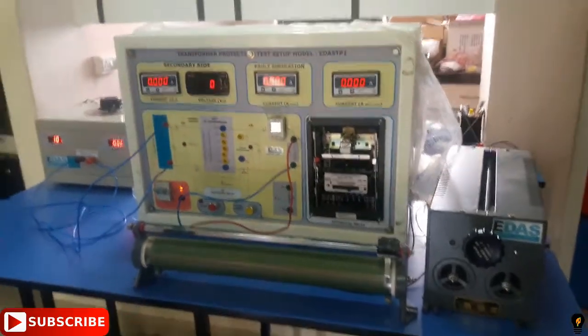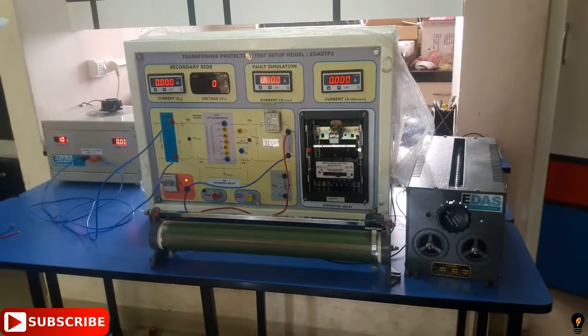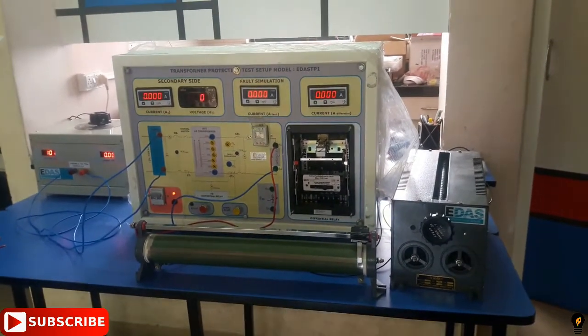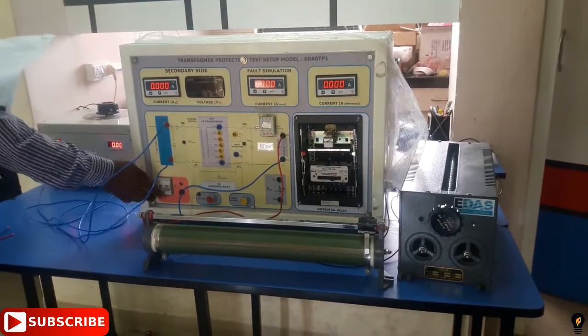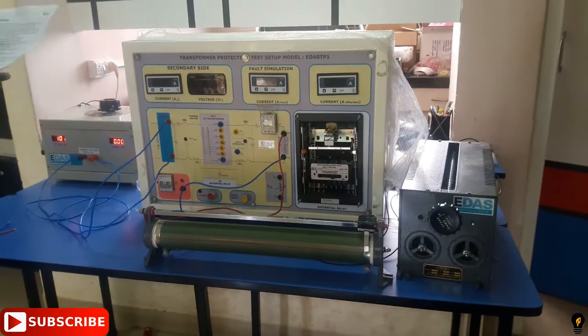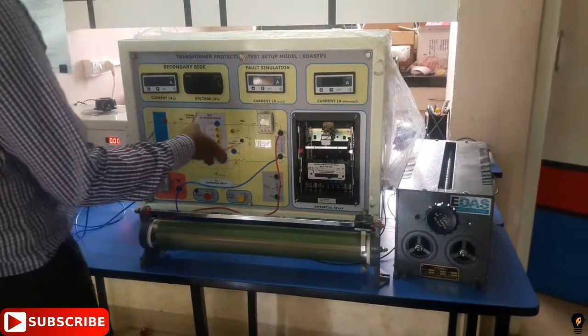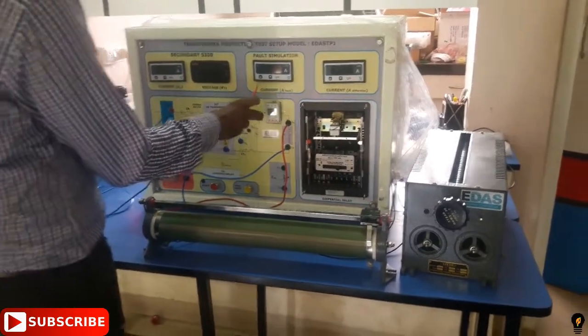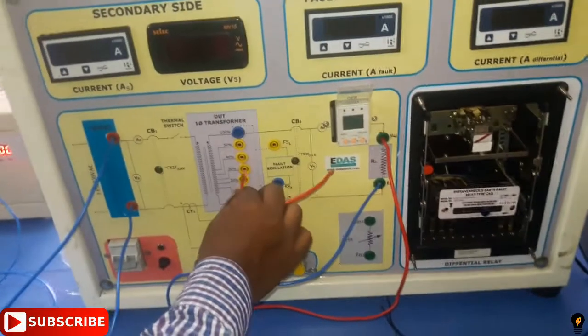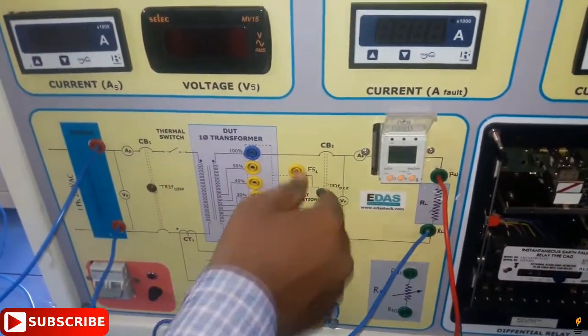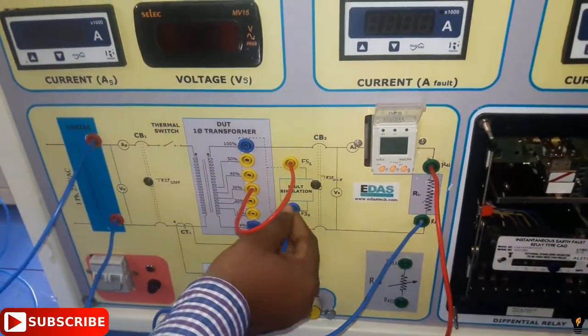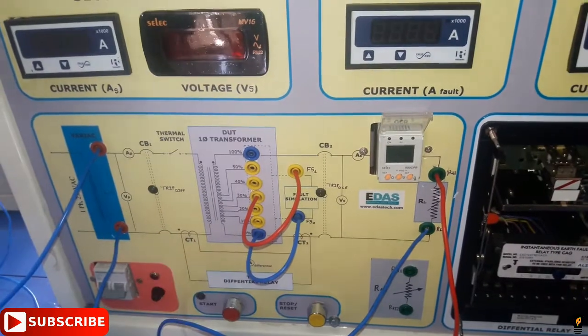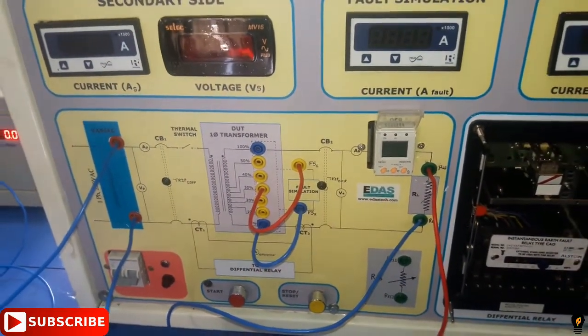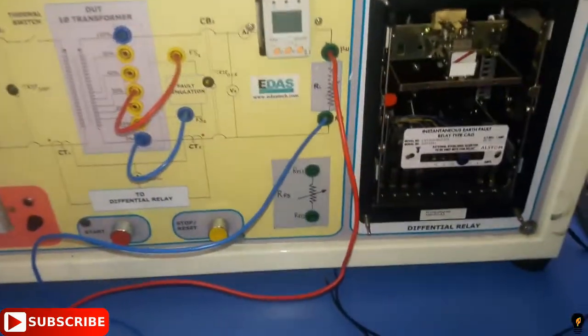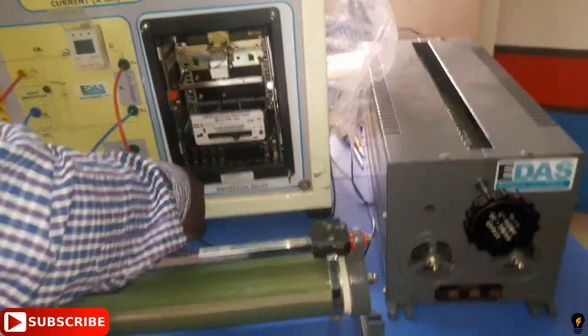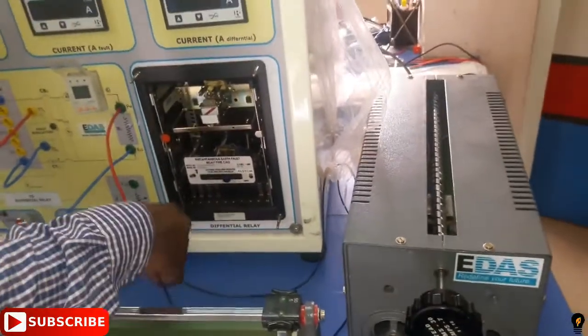Now we are going to create an interturn fault in the secondary of the DUT transformer. To do this, switch off the power of the TPTS unit using the MCB. Connect FS1 to 30% tapping. This is FS1 of the fault simulation block, connected to 30% tapping of the DUT transformer, and FS2 to 0% tapping of the DUT transformer. Connect RFS1 and RFS2 to the external RFS unit. This is the RFS1 fault simulation resistor.